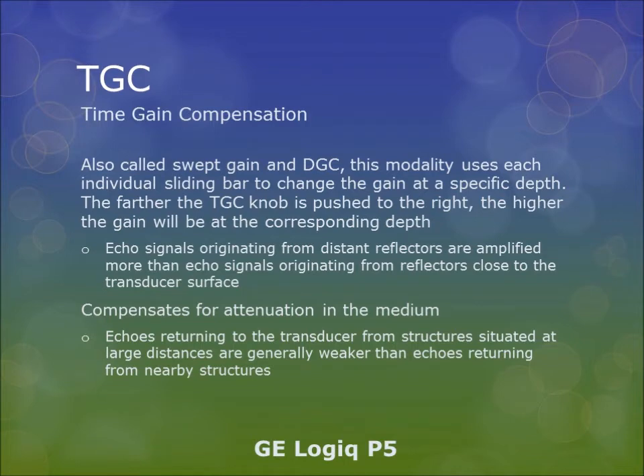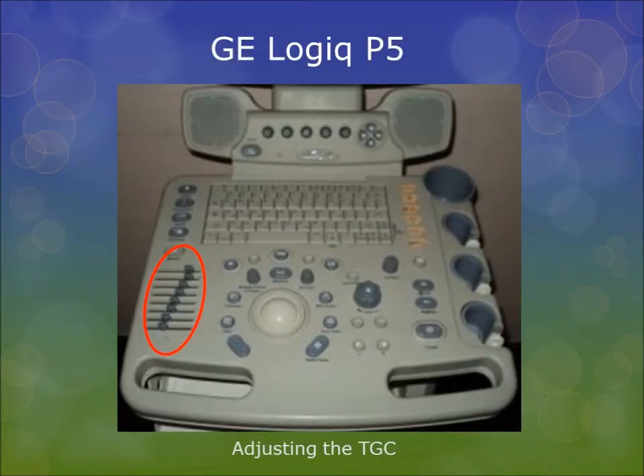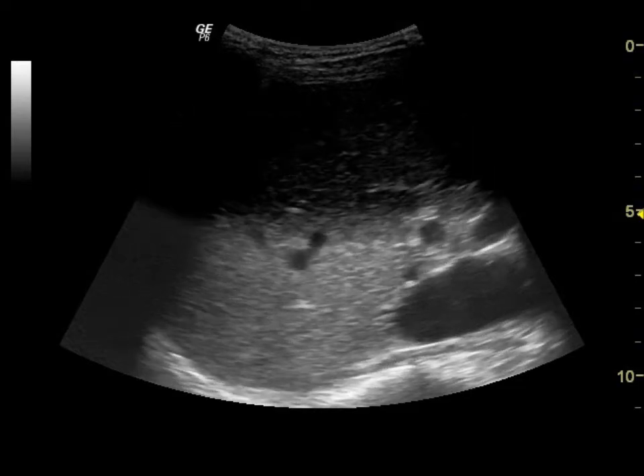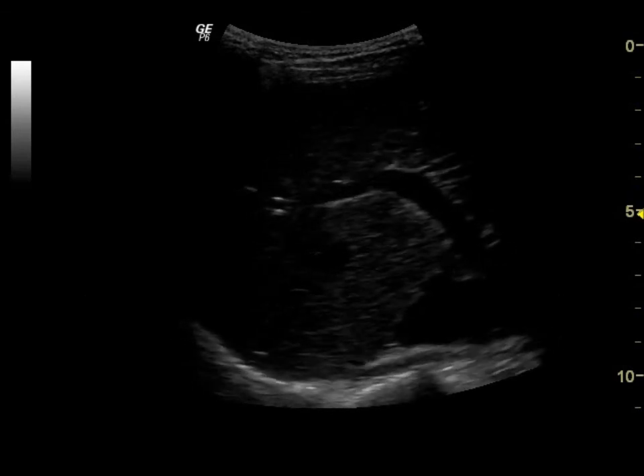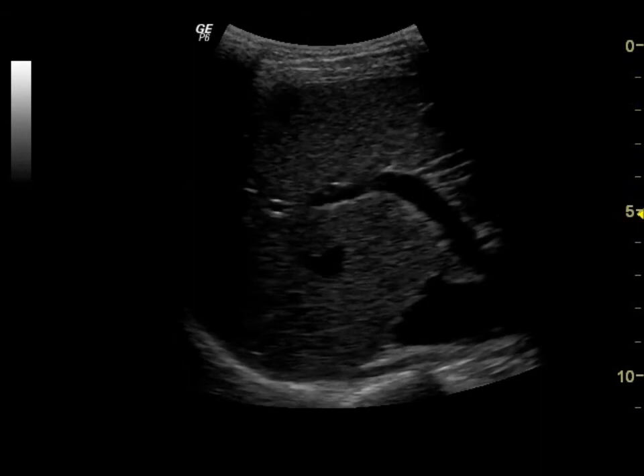Time Gain Compensation, also called Swept Gain or DGC, uses each individual sliding bar to change the gain at a specific depth. The farther the TGC knob is pushed to the right, the higher the gain will be at the corresponding depth. Echo signals originating from distant reflectors are amplified more than those from reflectors close to the transducer surface. TGC compensates for attenuation in the medium, as echoes from distant structures are generally weaker than echoes from nearby structures. As each TGC bar is moved to the left, gain at a single depth decreases; as each bar is slid to the right, gain increases at that depth.